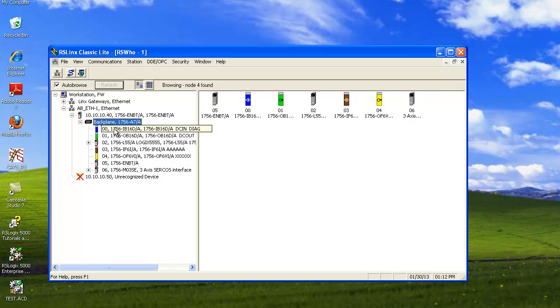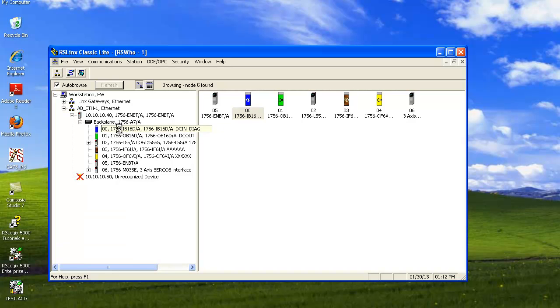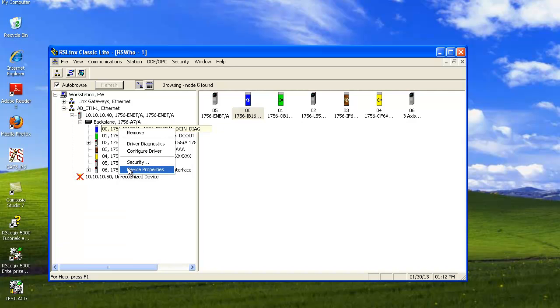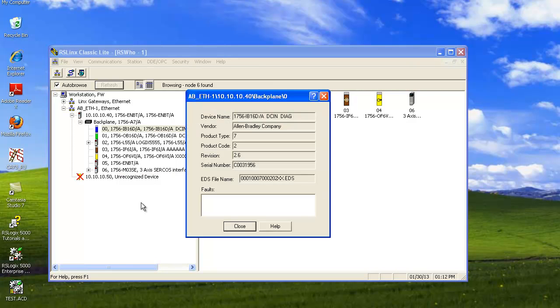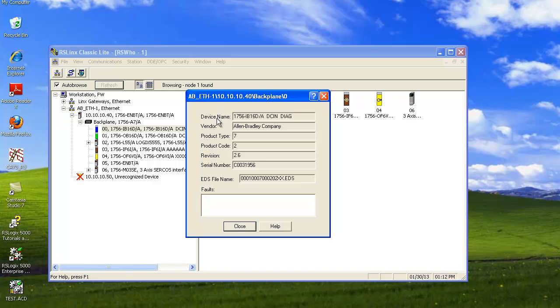And the important information here is to click on them. Left click on one of them, turn it blue, and then right click on it for Properties. Important information is needed here so that we can program it in RSLogix 5000. First of all you need the device name: 1756-IB16. And the I of course stands for input.